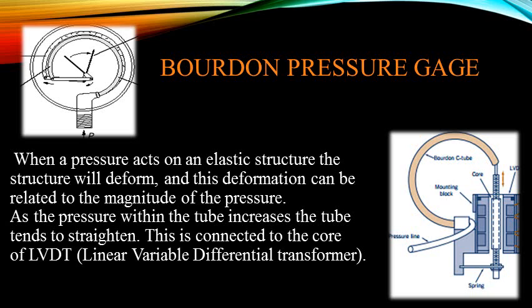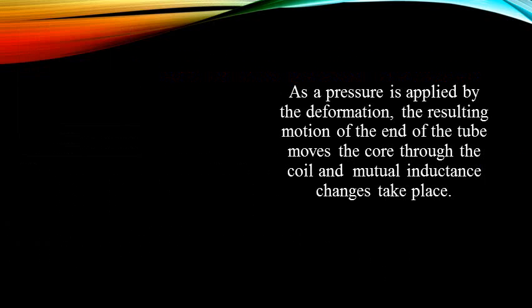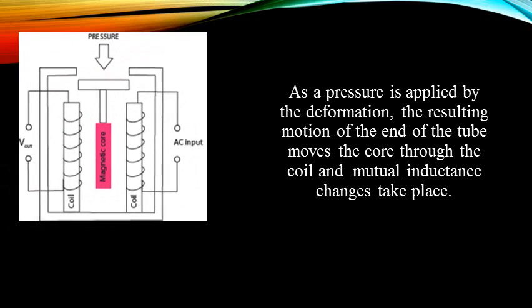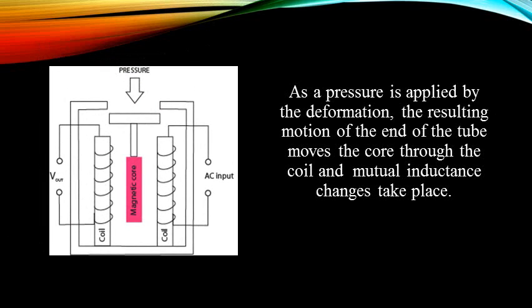This is connected to the core of the LVDT, the linear variable differential transformer. Relating this to the working of a pressure transducer, as pressure is applied, the resulting motion of the end of the tube moves the core through the coil, and mutual inductance changes take place.